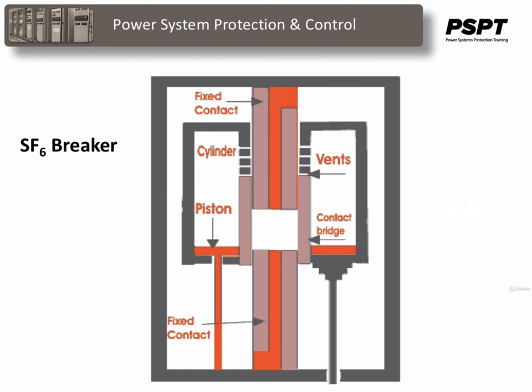The working of the SF6 circuit breaker of the first generation was quite simple. It is, to some extent, similar to an air blast circuit breaker. SF6 gas was compressed and stored in a high pressure reservoir. During the operation of an SF6 breaker, this highly compressed gas is released through the arc in the breaker and is collected in a relatively low pressure reservoir. Then it is pumped back into the high pressure reservoir for reuse.